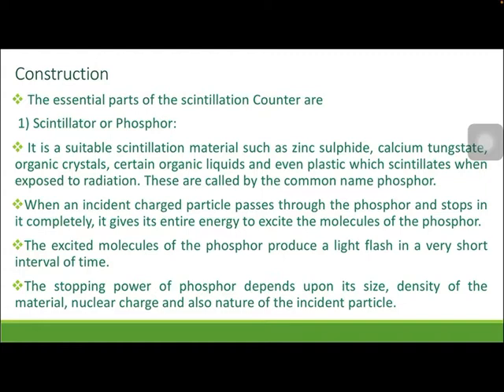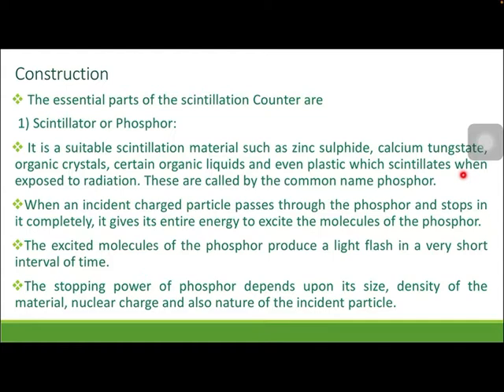In the construction of this scintillation counter, there are three essential parts. The first one is the scintillator, which is nothing but a phosphor material. It is a suitable scintillation material such as zinc sulfide, calcium tungstate, organic crystals, certain organic liquids, and even plastics which scintillate — meaning they emit light when exposed to radiation, whether alpha, beta, or gamma radiation. These are called by the common name phosphor.